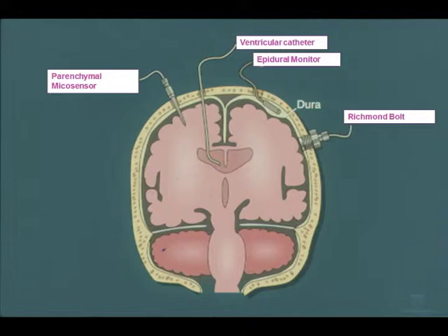It's simply a catheter that's stiff, that contains the CSF, that's connected to fluid-filled tubing to a pressure transducer that's placed at the foramen of Monro, or close enough, sometimes we'll say ear level, right? That's actually the device that Lundberg used in the 1950s in Lund, Sweden, when he wrote his classic descriptions of ICP monitoring and the A waves and the B waves.